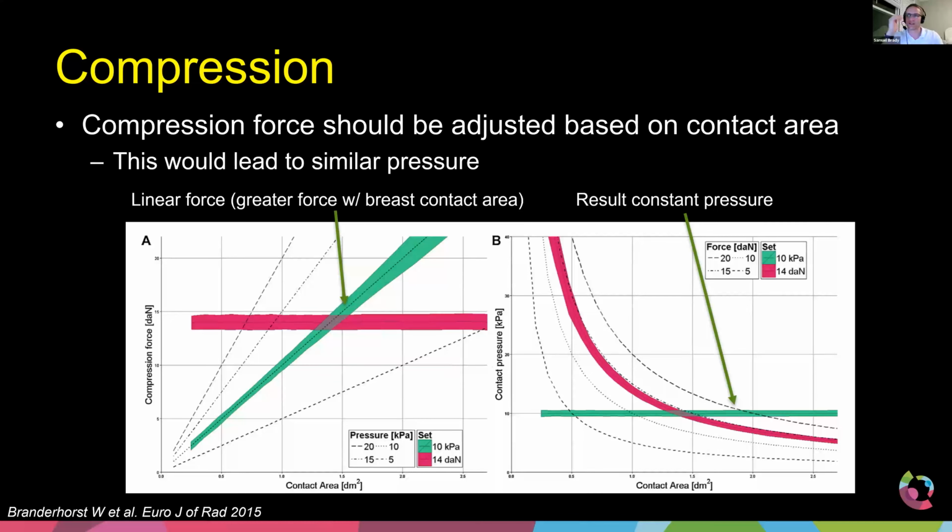And so basically by telling the system these things, the system would know, okay, if it's a smaller breast, potentially more dense, then it would know to give a different target force. So as they step on the pedal and the compression pedal comes down, it would help give them feedback as to, okay, now you've got the right force, instead of going all the way down to 25 or even 40 pounds. I see. So that clears up a lot of stuff.